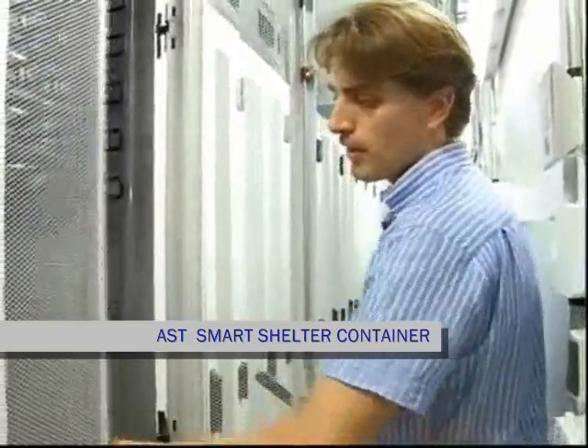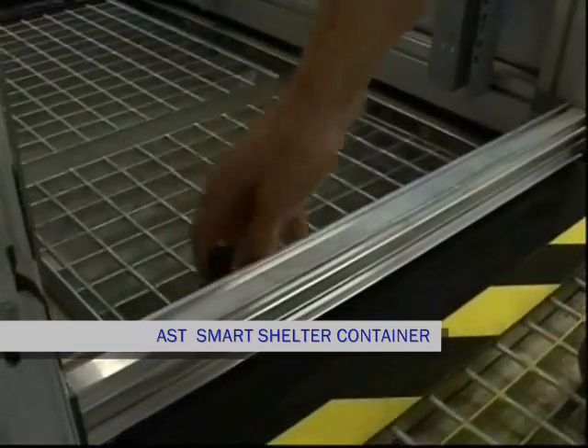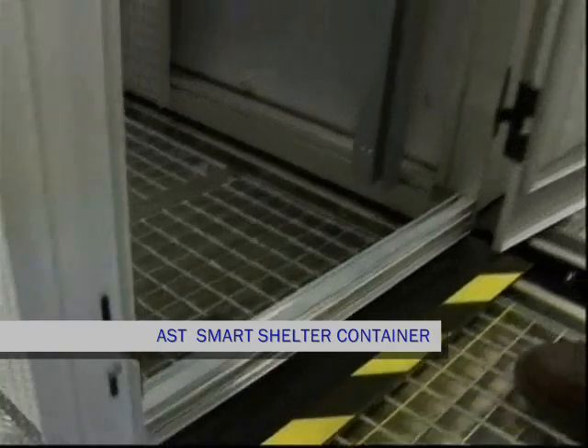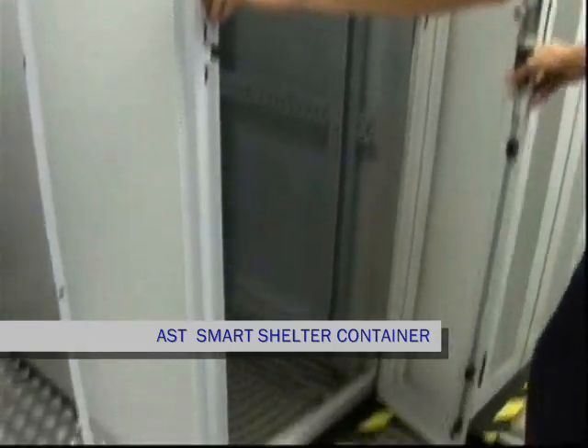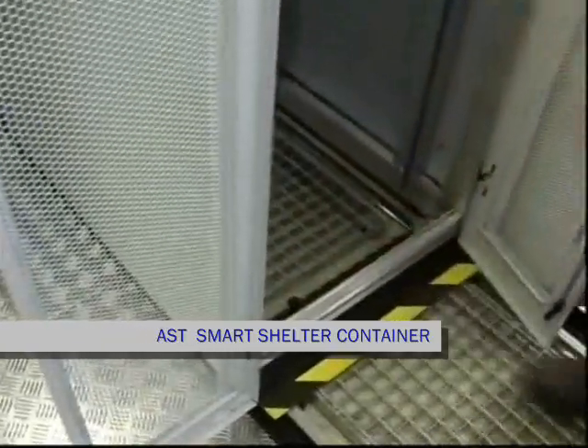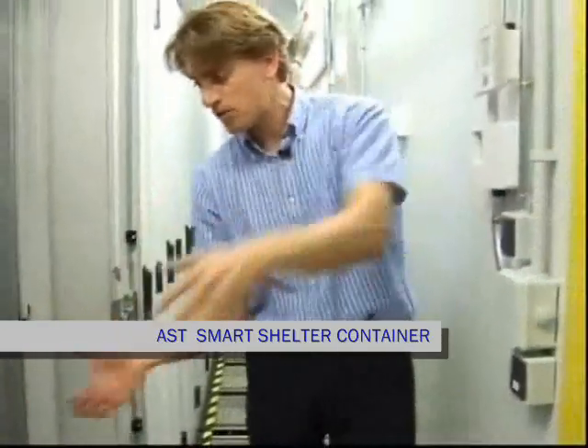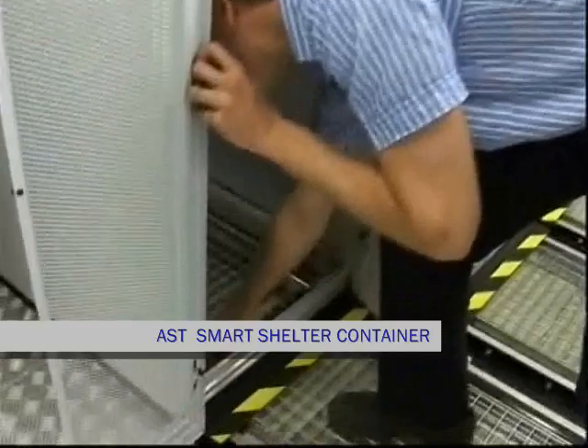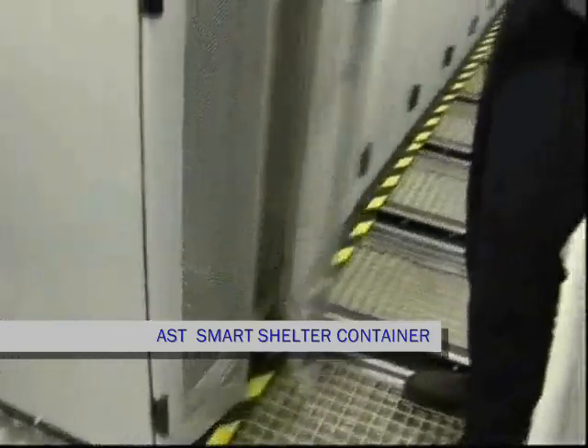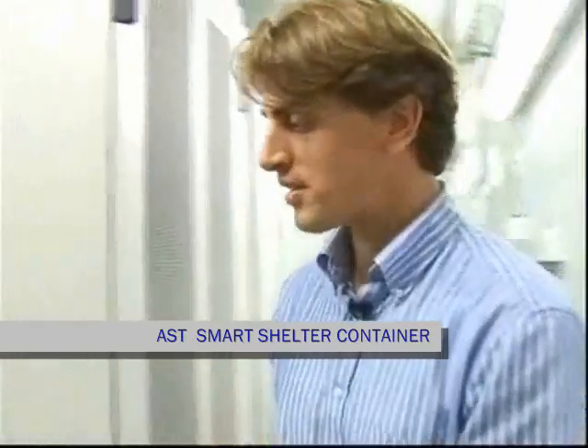Our rack system is configured in a way that allows perfect access on the front side and on the back side of the rack with our special railing system. Our railing system has a braking system. I just release the braking system in order to allow nice and easy access on the front to install really deep servers. We have a nice space here of 1 meter in order to install really deep servers of any hardware manufacturer on the market. If I release the brake again, we'll have a look at the backside of the rack in order to understand our specifications, or the space that we have available as well on the backside.